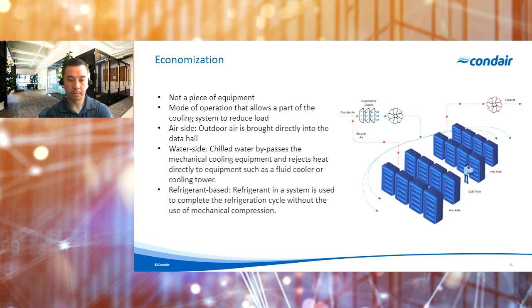In air side economization, outdoor air is brought directly into the data hall when temperature and humidities are within an acceptable range. With this type of system, the outside air can also be cooled and humidified with equipment such as an evaporative cooler to increase the potential hours for economization. In water side economization, chilled water from a cooling system is either fully or partially bypassed around the mechanical cooling equipment and allowed to reject heat directly to equipment such as a fluid cooler or a cooling tower when those pieces of equipment are able to provide sufficient cooling.